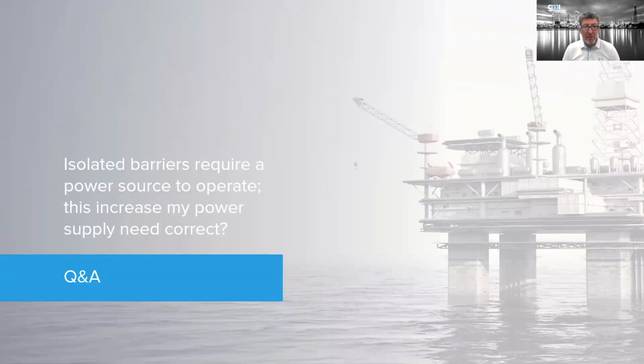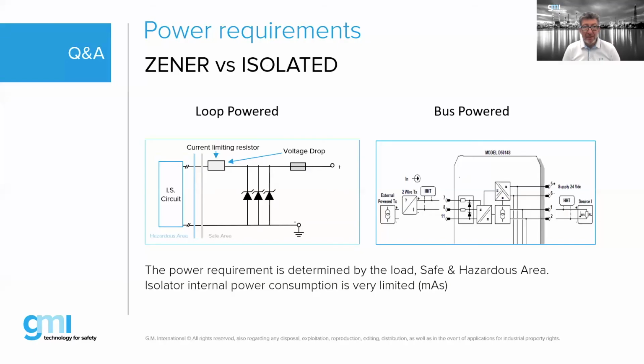Isolated barrier requires a power source. So does this increase my power supply need? I don't believe so, 100%, but we try to put together this idea where you have Zener barriers basically loop power, but you get a lot of voltage drop across the current limiting resistance. In the isolated barrier, it is bus power, so you get a more defined power output. So if we say you get 16 volt, you get 16 volt here. It really depends on the impedance of this resistance. In reality, a Zener barrier or an isolated barrier power requirement are basically the same.